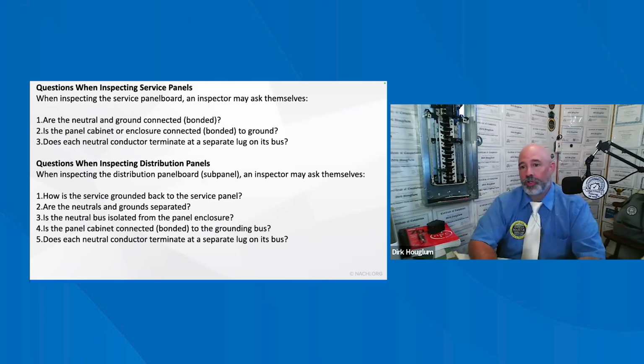Every structure is required to have a grounding electrode system. If they are present in the structure, they must all be bonded together. If a detached structure has a remote distribution panel located in the structure, then it requires a grounding electrode system of its own, 2008 NEC.